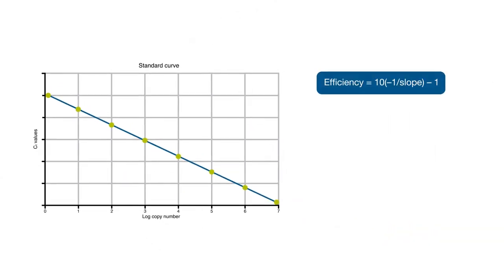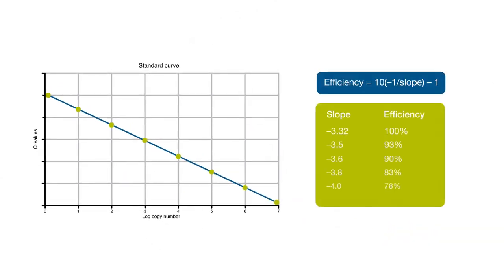The last step to ensure that your primer set yields usable, reproducible data is to make sure PCR efficiency is within the 90 to 110% range. You can do this by simply running a standard curve with at least five logs of input DNA and using the instrument software to calculate the PCR efficiency.